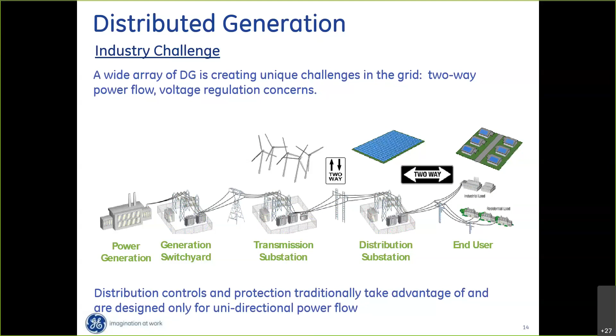We can integrate distributed generation into the grid, either at the transmission level, distribution level, or the end user level. The challenge with distribution is that we designed the distribution system to have electricity flowing in one direction, from source to load, and we set our protective relays that way, assuming flow from source to load only. Now with distributed generation, we have electricity flowing in two directions.